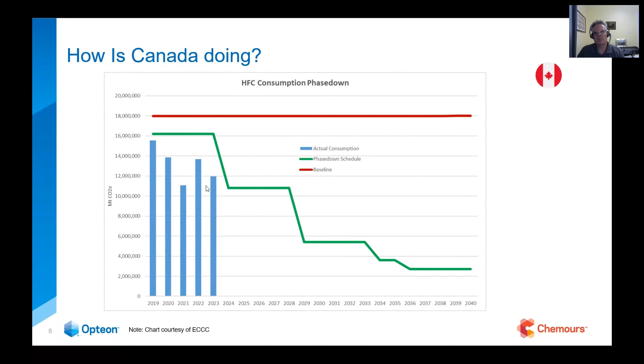The second part of the Canadian regulations is the segment-specific controls. The US had implemented similar numbers, and some states had gone along with very similar regulations. For centralized systems, we're already not allowed to use GWPs greater than 2200 in new equipment. A couple of new ones coming up at the end of this year will be chillers, air conditioning, and refrigeration. Chillers will have a GWP limit of 750 for new equipment, and mobile reefer trailers and that type of thing will be limited to 2200. It's interesting because the new US regulations propose similar values to this.